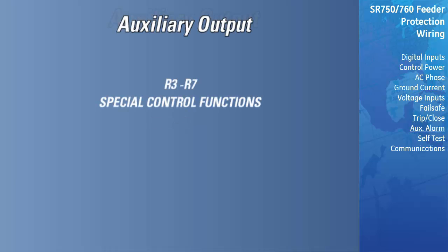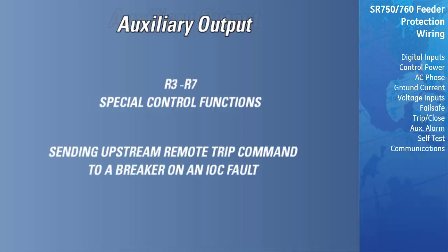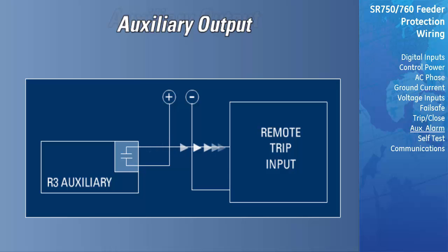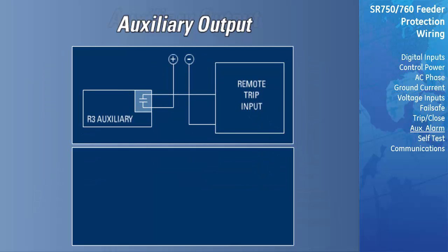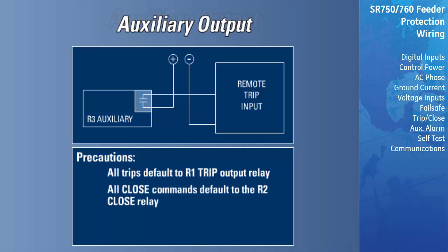Auxiliary relays R3 through R7 are intended to be used for special control functions, such as sending an upstream remote trip command to a breaker on an IOC fault. It is a good idea to decide early on what function each of these relays will perform to avoid assigning conflicting functions to the same output. To ensure conflicts in relay assignment do not occur, some precautions have been taken. All trips default to the R1 trip output relay. All close commands default to the R2 close relay.